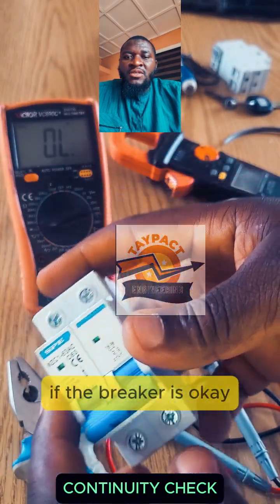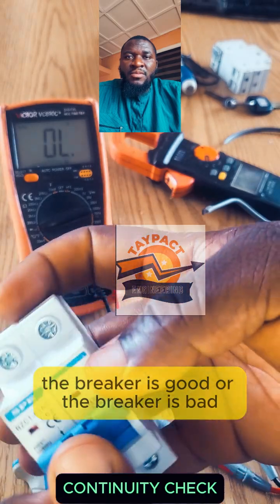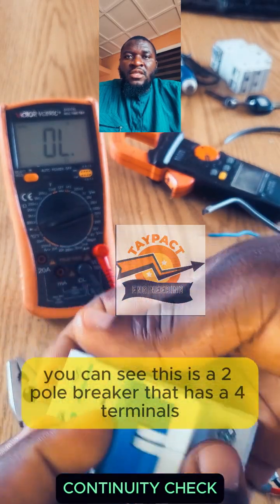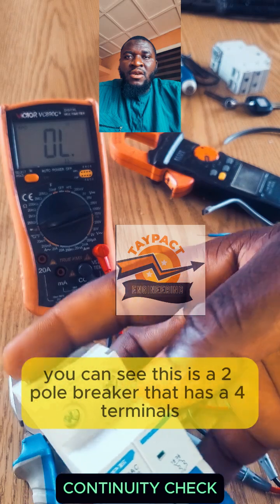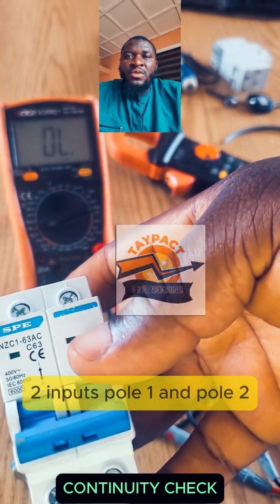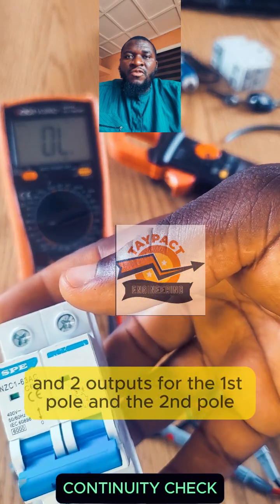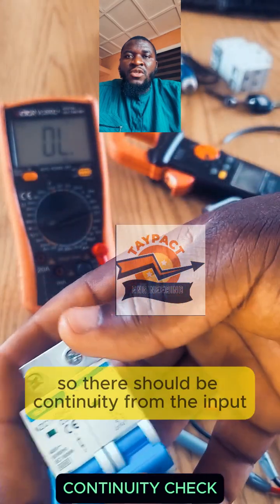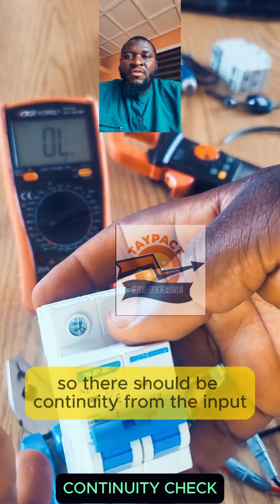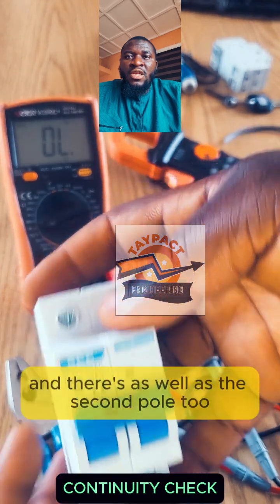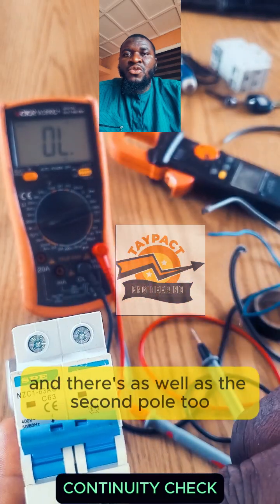So as we want to test a breaker, to know if the breaker is good or bad, you can see this is a 2-pole breaker that has 4 terminals: 2 inputs, pole 1 and pole 2, and 2 outputs for the first pole and the second pole. So there should be continuity from the inputs to the outputs, as well as the second pole too.